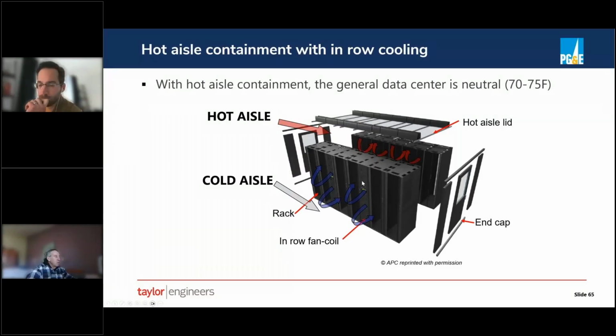And so the computer racks are pulling air from cold, blowing it into hot. The in-row coolers work in the opposite direction. They pull air from the hot aisle and blow it into the cold. So you can basically put a lid and doors on the hot aisle and use your in-row cooler. And it's a form of what we call close coupled cooling. You're putting your cooling very, very close to your racks.